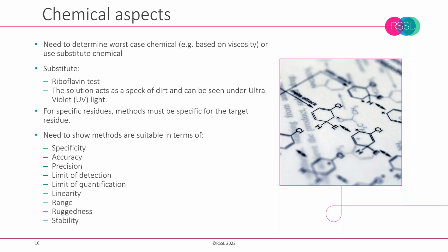Sometimes a substitute chemical that's used is riboflavin, but in these sorts of cases, either the use of a substitute or the selection of worst case requires justification, considering things like physicochemical binding, viscosity, and parts of the equipment that are going to be most exposed. A very careful rationale needs to be constructed.